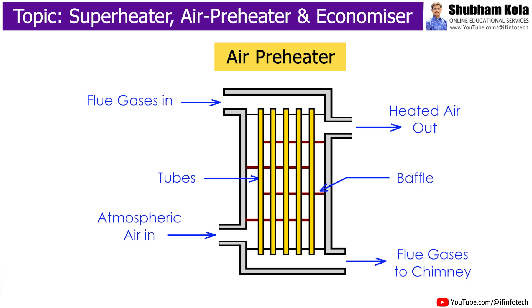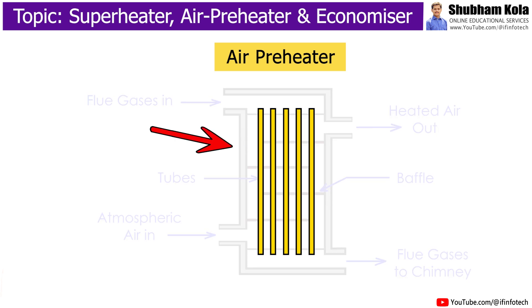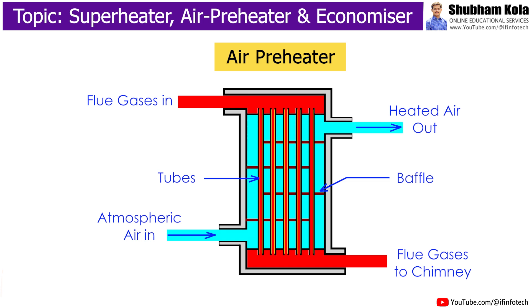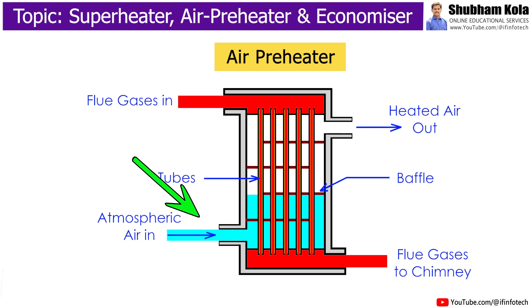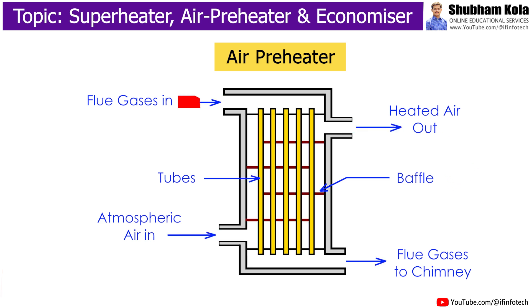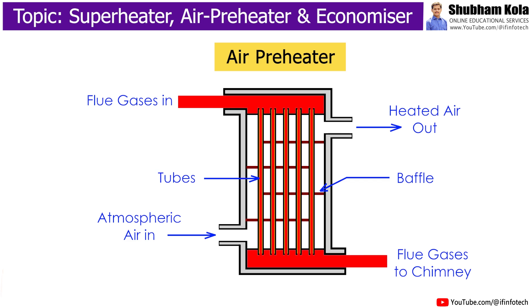The air preheater consists of straight tube bundles where hot furnace gases pass through the tube bundles, transferring heat from the exhaust gas to the air around the tubes. The ambient air is forced by a fan at one end of the preheater tubes and heated air comes out at the other end. This increased temperature air is supplied to the combustion chamber for combustion of fuel. The main purpose of the air preheater is to recover heat from exhaust gases to improve overall efficiency.